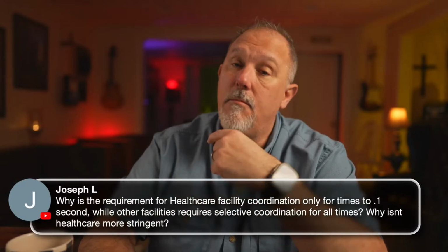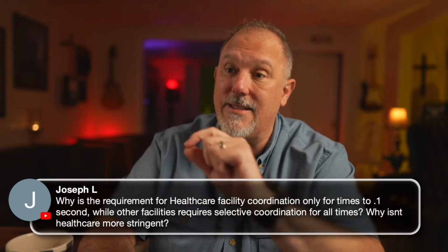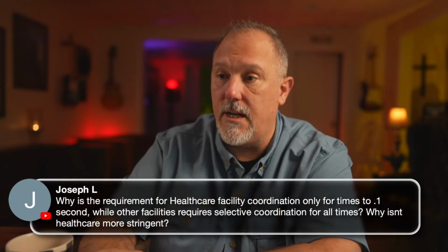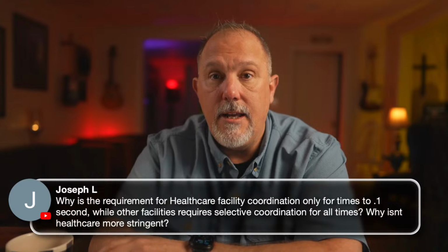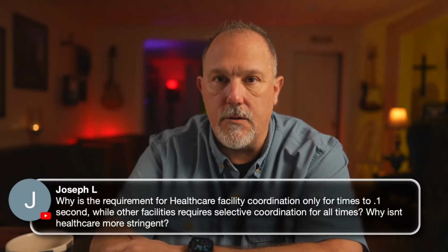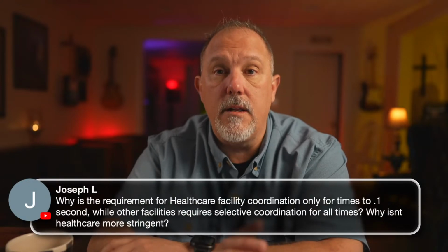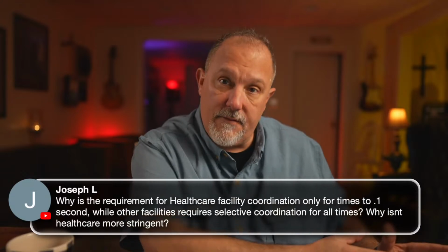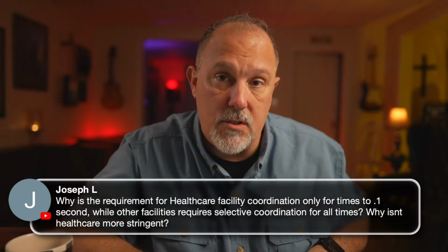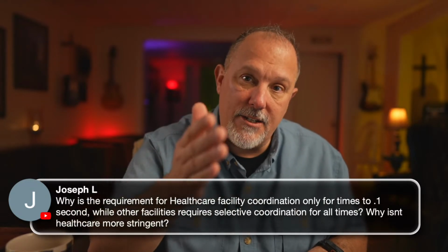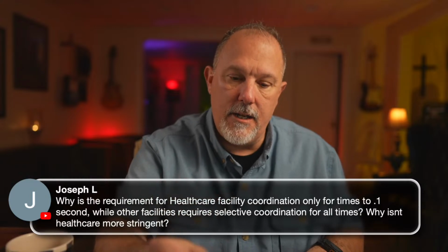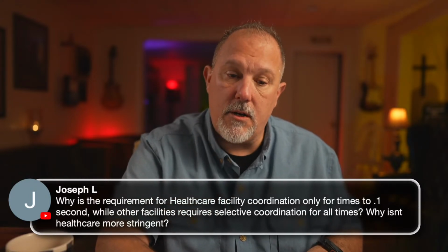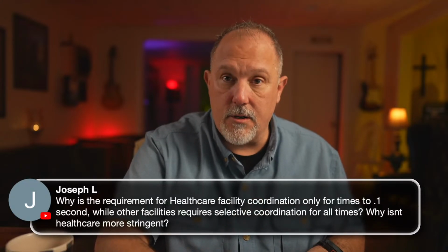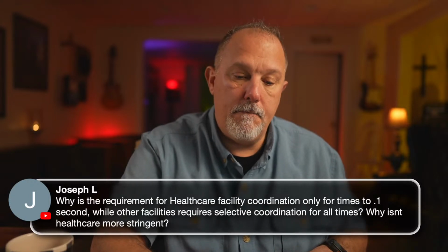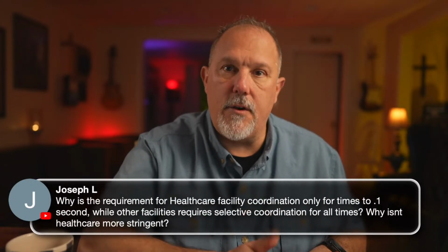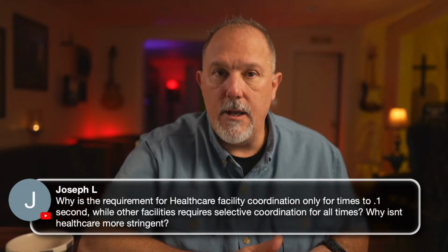And that's my opinion only, because that's what I'm going to give you as a power systems engineer. I would not design a system without an evaluation of current. Even if I said, look, I'm going to coordinate to a ground fault current, that would be legitimate. I'm drawing the line, and I could back up. I could take IEEE information, and I could tell you it's the most common fault in a power distribution system. It is a ground fault current. I could go out on that limb and say I'm making an engineering decision to coordinate to ground fault current because 3-phase bolted fault currents never occur or hardly ever occur in a normal operating power distribution system. Ground fault currents are your most common fault currents. I could make that argument.